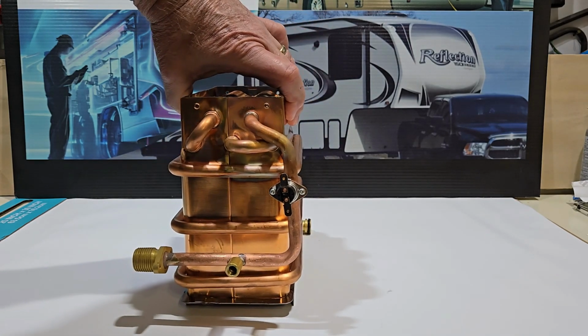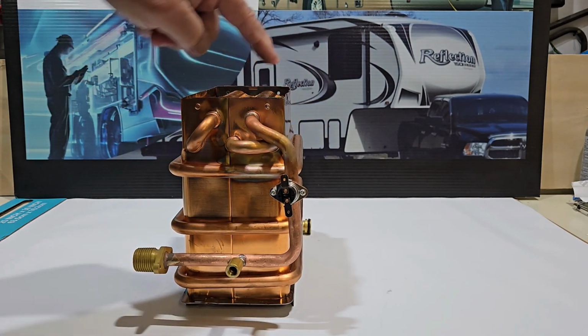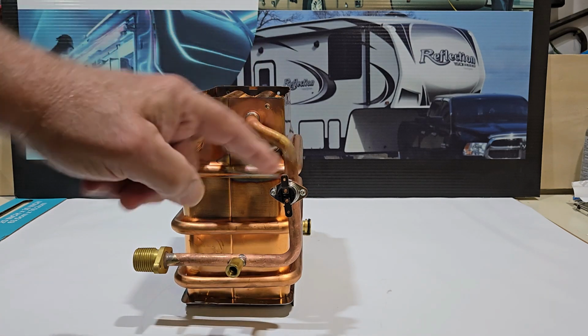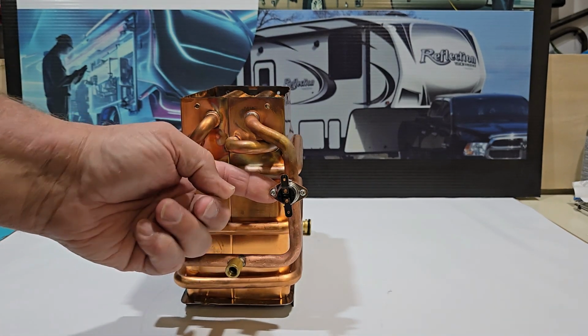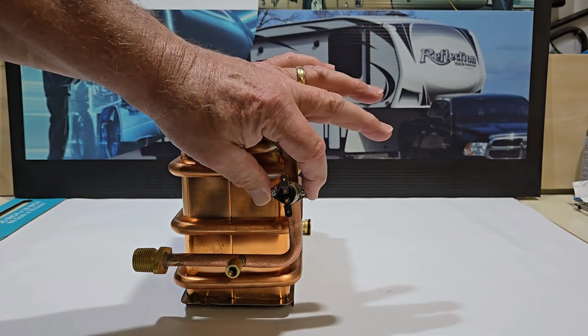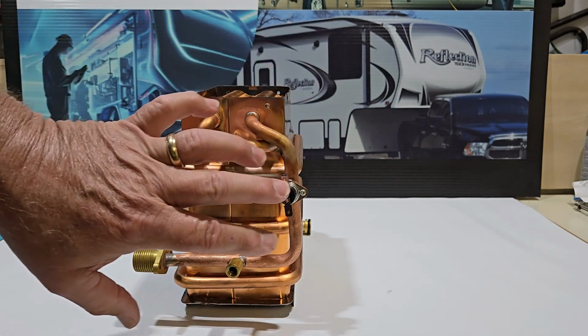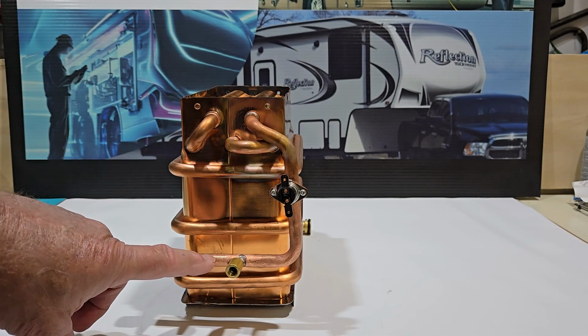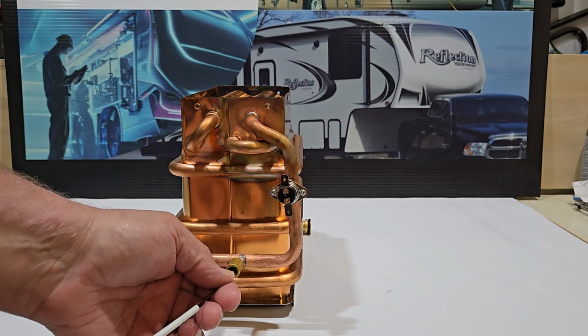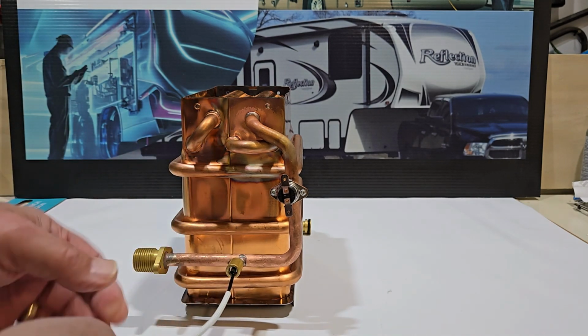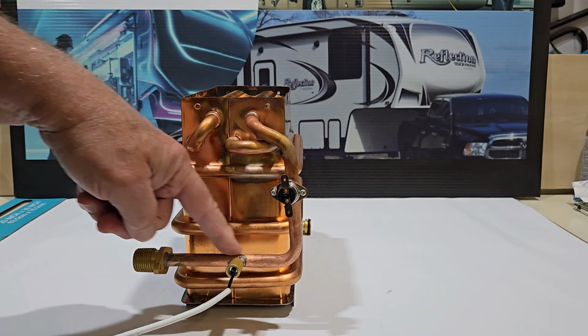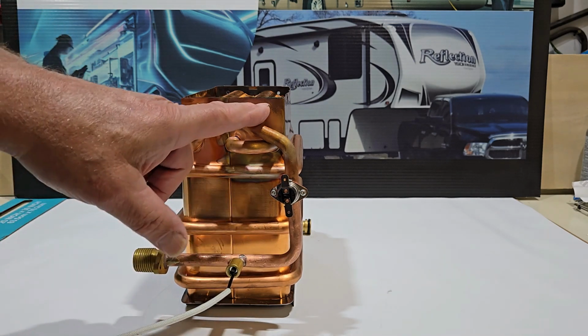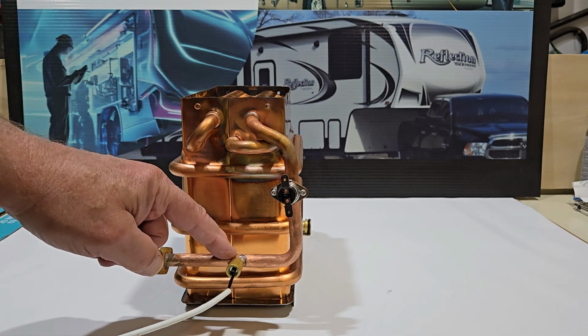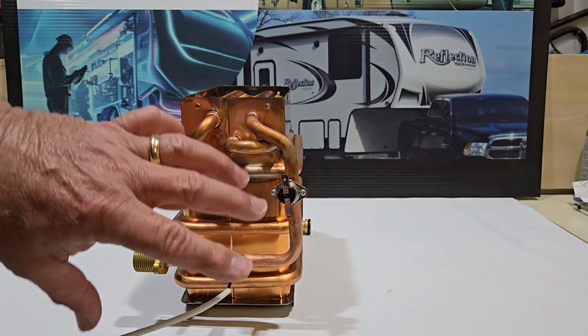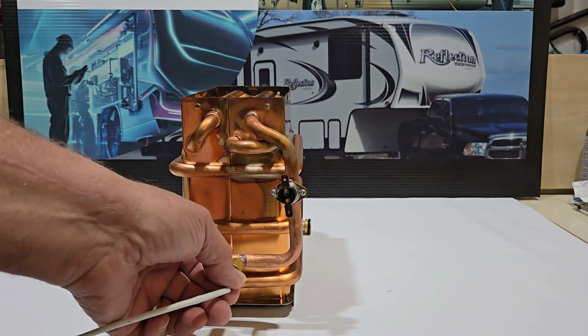On the output side, you can see right here, this is the last of our loop. We have an over temperature switch. If this exceeds whatever the rated temperature is, it's going to open and immediately shut down our water heater. And right here we have another temperature probe, something along these lines would sit in there and actually touch the water as it's going by. This acts as our temperature sensor for the output water, telling us how hot the water coming out of this heater is.